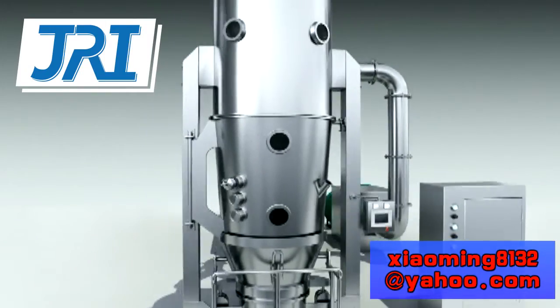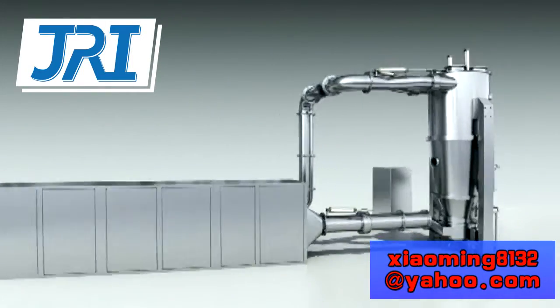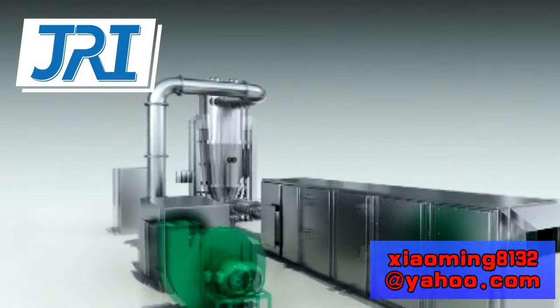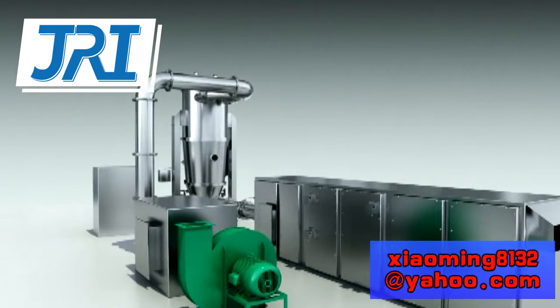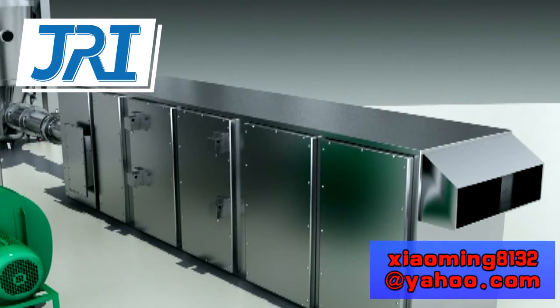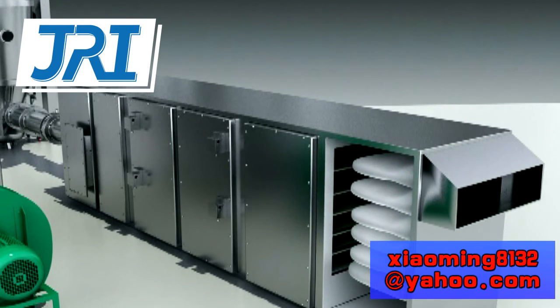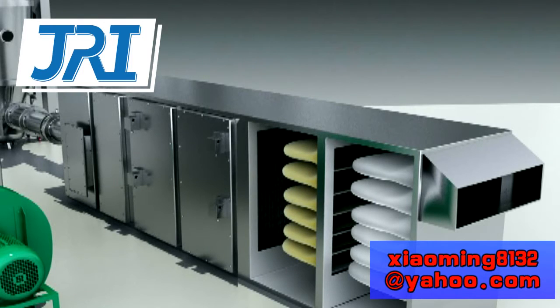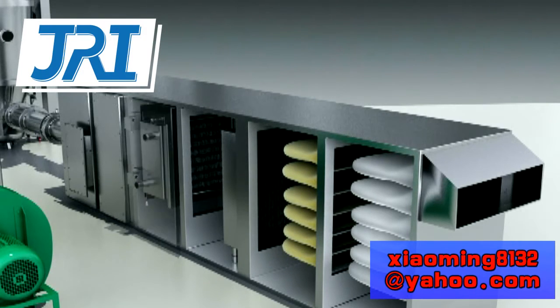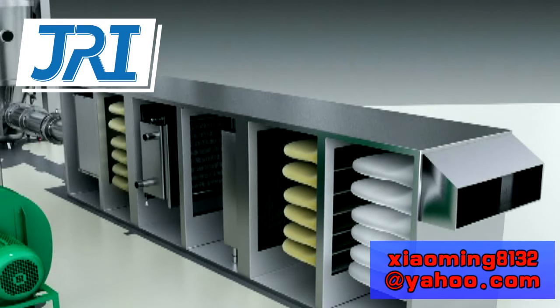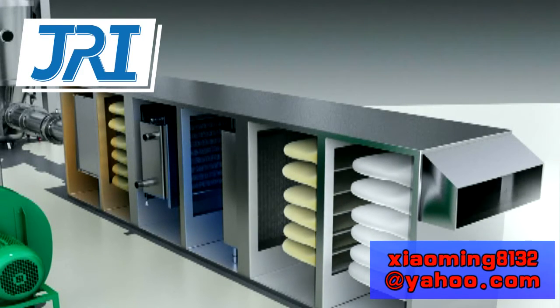Air inlet system. The air inlet opening is normally in the auxiliary machine room or outdoors. Air inlet system, also known as the air inlet handler, normally consists of pre-filter, post-filter, steam heat exchanger, sub-high efficiency filter and or HEPA filter. Dehumidify with preheating arrangements and air inlet bypass of heat exchanger are available on request.